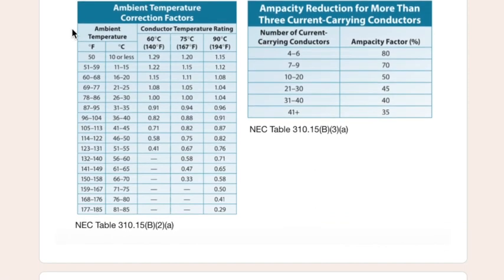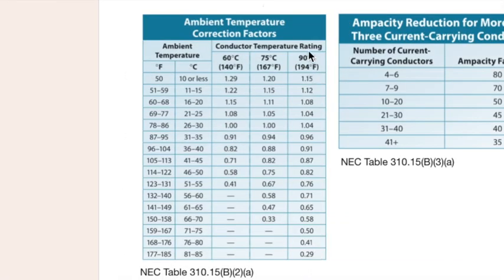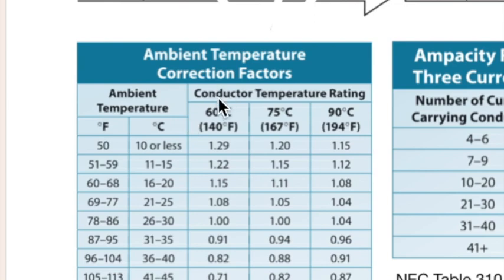So the next thing we need to talk about is our ambient temperature correction factors chart here. In the code book, this is NEC table 310.15(B)(2)(A). So anyway, we have our ambient temperature, Fahrenheit and Celsius. And then we have conductor temperature rating.